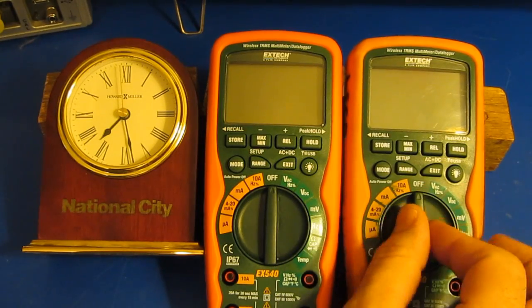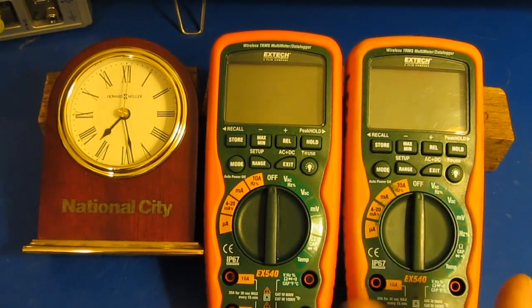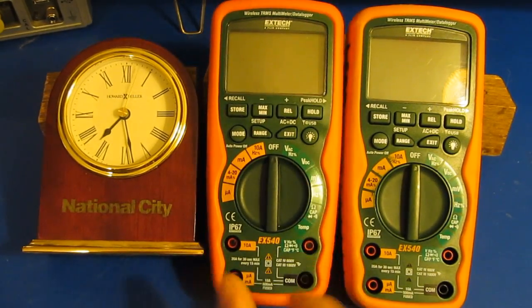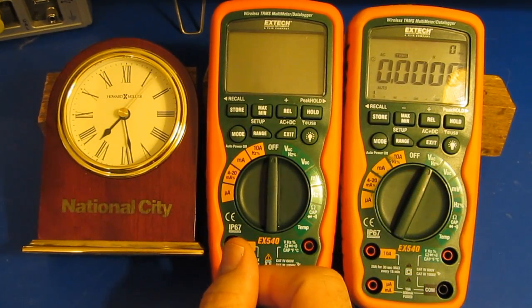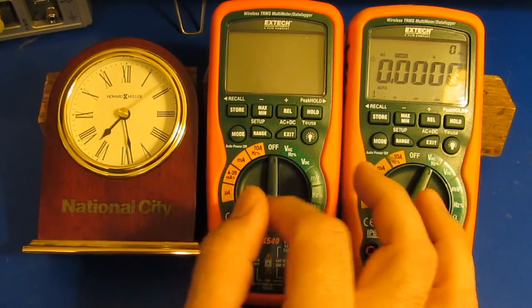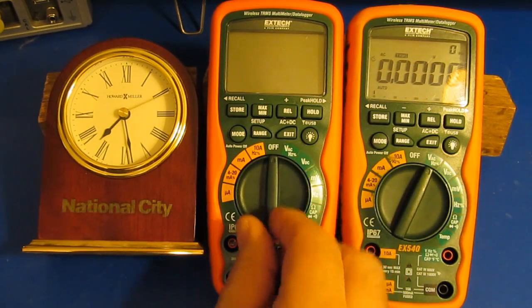So if I take our original meter and I select it to volts AC, and you can see I don't have any leads on either one of these meters, you can see the meter reads zero volts. And it's very solid at zero.